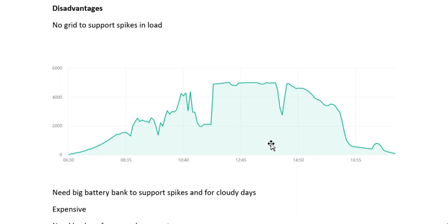So what does that mean? Well, it means that when you start something, for example a big pump, it's going to have a big spike. So let's say even though a water pump might have a rating of 1000 watts, it could spike up to 2000 watts in the beginning. This is what we call inductive load. Now if your solar system is already sustaining a load of many thousands of watts, and then suddenly you add many thousand more on top of that, you could overload the inverter, and then the solar system will shut down. You have to turn something off and restart to make it work again.